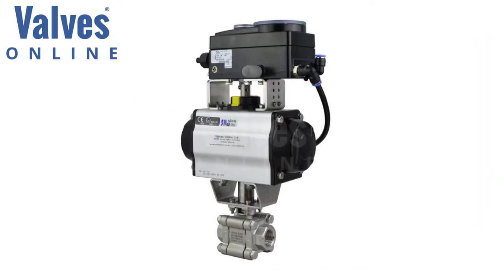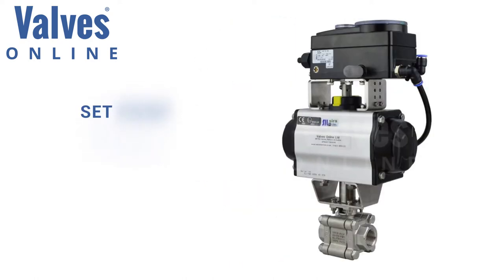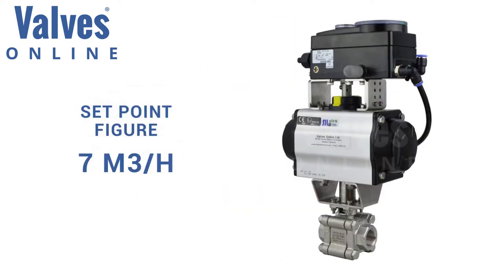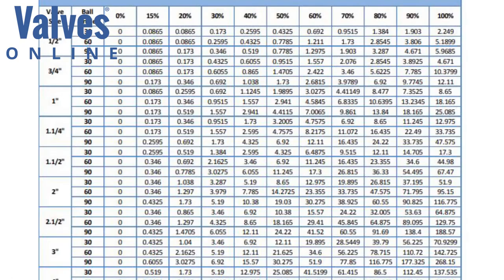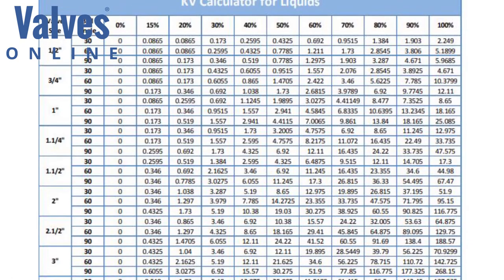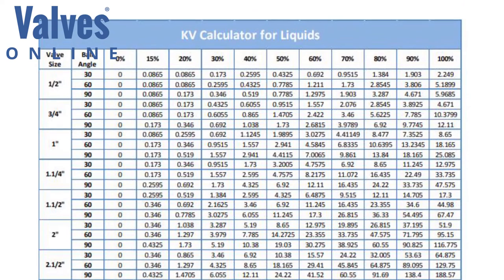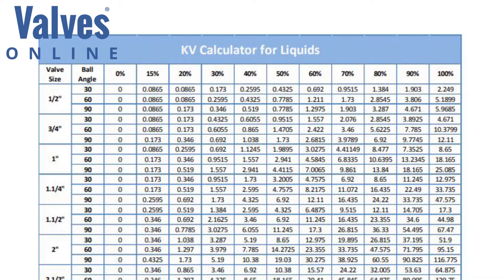Here's an example. An engineer wants to control or maintain a flow in a pipeline. The engineer has a set point figure of seven cubic meters per hour which meets the requirement. On the chart, the engineer looks for a figure that matches or is close to the flow requirement of seven cubic meters per hour, and finds a figure of 6.8335, which is close to what is needed and roughly matches the pipe diameter currently in the process.